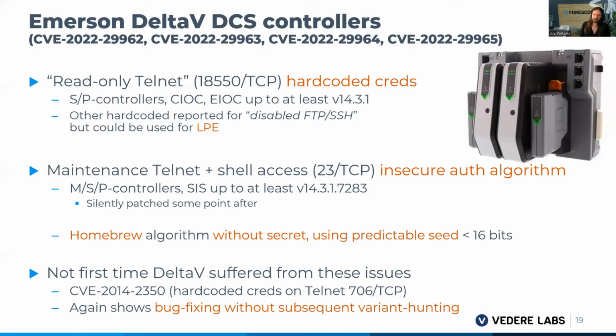In addition to these hard-coded credentials, there is a maintenance telnet interface that offers access to a shell on these controllers. This interface uses an insecure authentication algorithm present on the M controllers, the S controllers, the P controllers, and the safety instrumented controllers, up to a very recent version, after which it was silently patched. This authentication algorithm consists essentially of a homebrew crypto algorithm, which is not really cryptographically secure in any way.